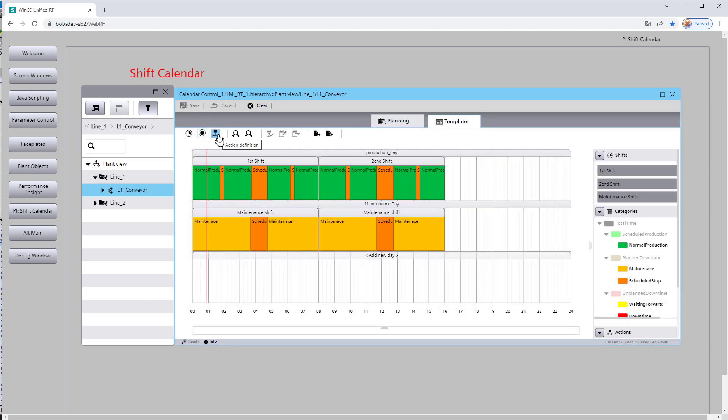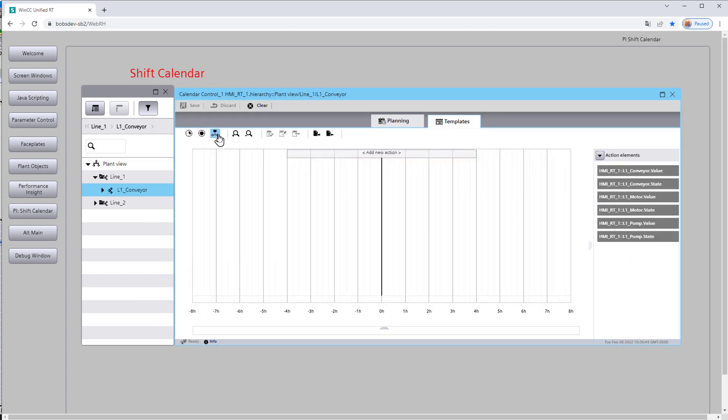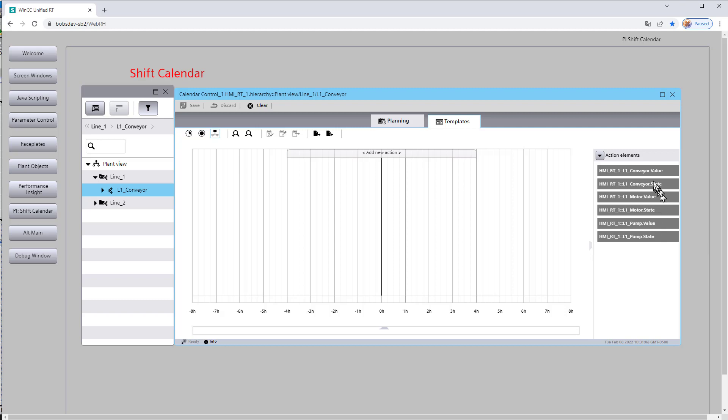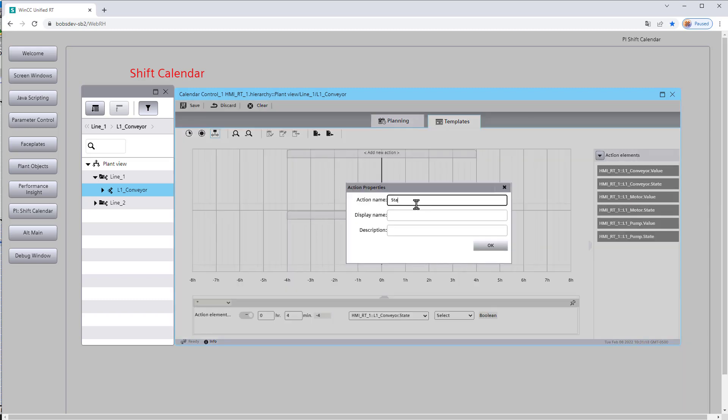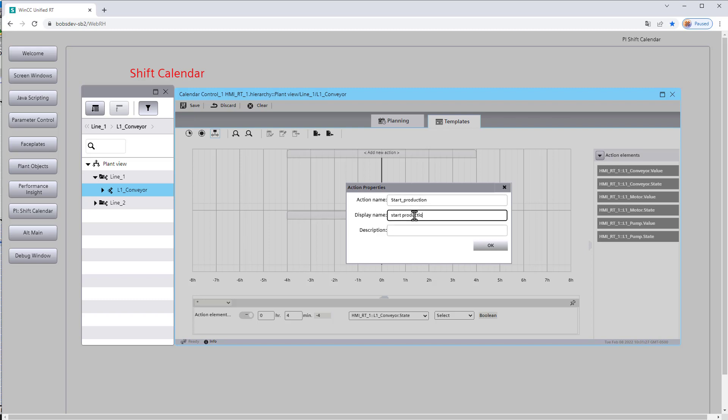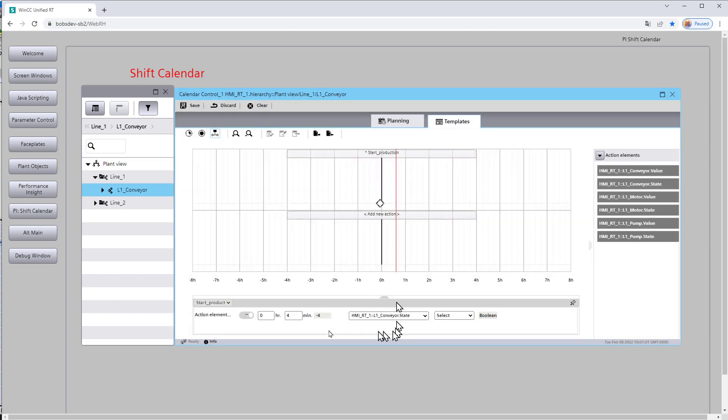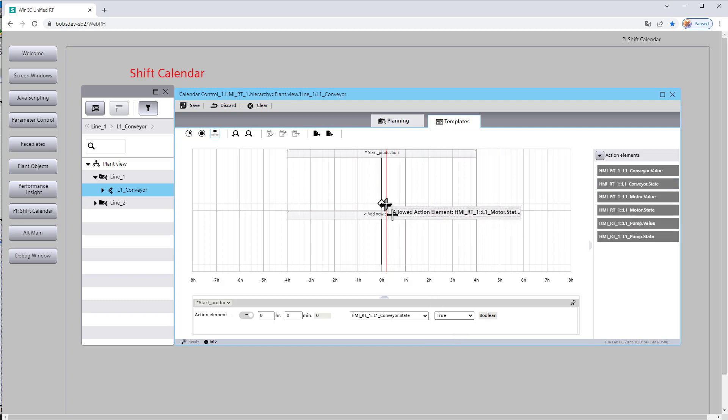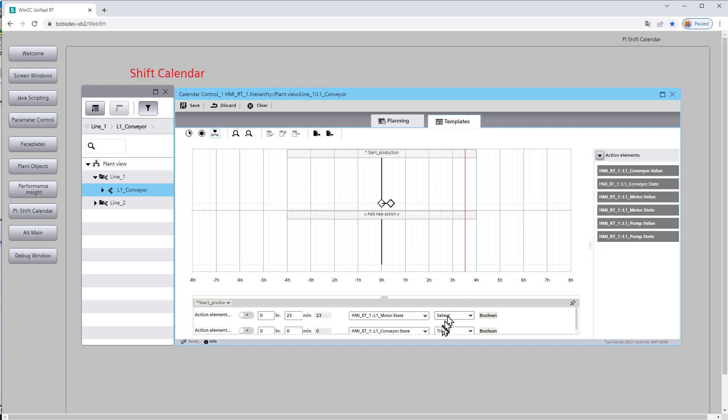Another thing that we can do is actions. And these are actually a pretty neat feature. They allow you to do stuff with your load interface tags from your plant objects when a shift starts or ends or whatever you want to do. So let's say that when a shift starts or when a day starts, then we need to turn our conveyor on. So we can just pull this out. Let's call this start production. And when I drag this out, it's going to give me the start time and I can choose the state. So let's say that our conveyor gets turned on.